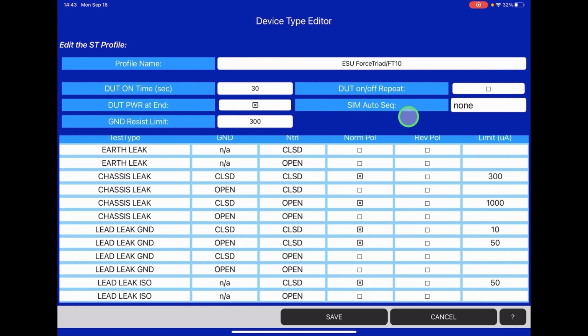Sim auto sequence is for simulation auto sequence. Of course, we don't need to do that, so we'll leave that as off and none. The next test is ground resistance test, or the ground bonding test as it may be referred to. We've set the limit per the manufacturer's requirements to 300 milliohms.